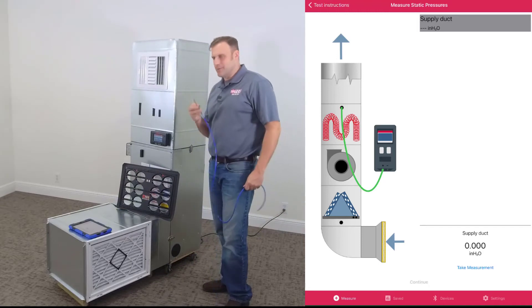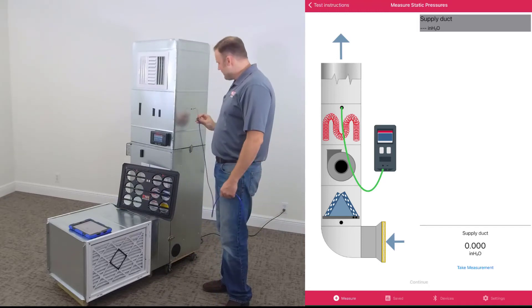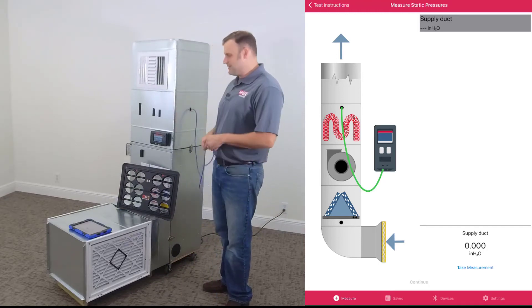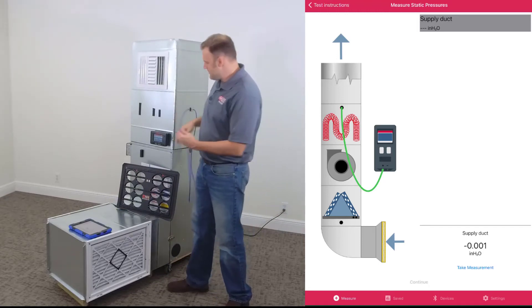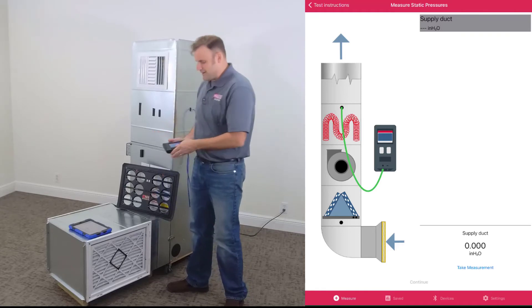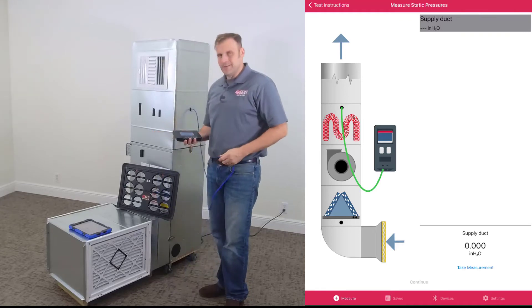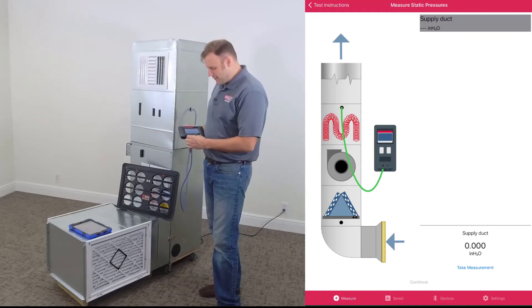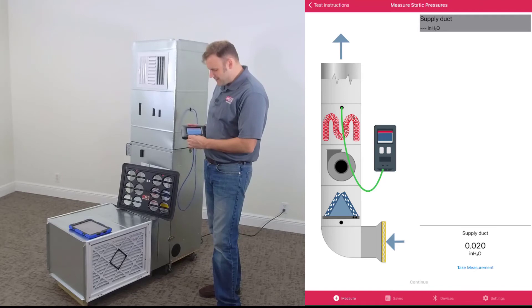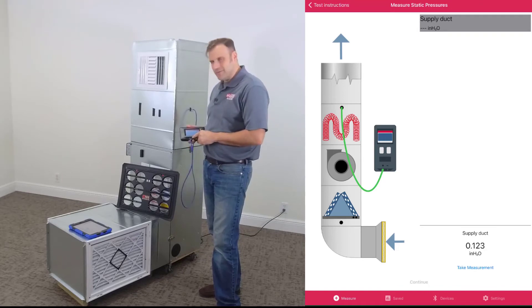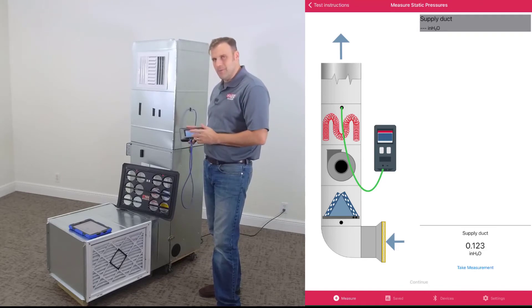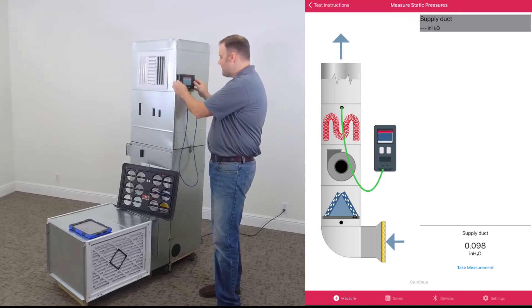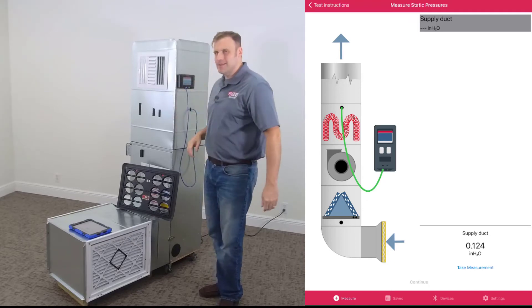Now we can begin that test. So let's take our static pressure probe, put it in the supply plenum against the direction of airflow. Let's take our DG1000 gauge, hook up the hose to the first port, leaving the second port of channel A open as a reference. Mount that gauge right there.